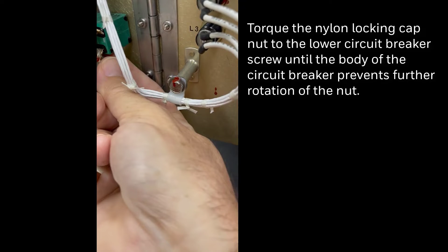Very simple. Next, we take the nut cap and thread it onto the offending screw in the circuit breaker. This is quite easy to do. There's no torque requirements; you just go until the nut stops and it's completely secured.